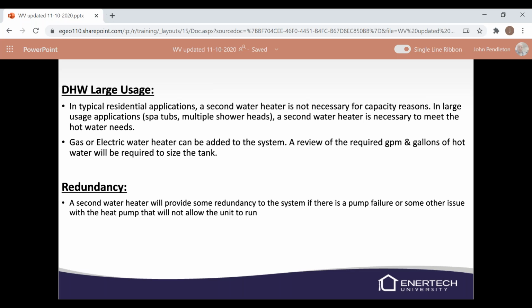Domestic hot water. In typical residential applications, a second water heater is not necessary for capacity reasons, but for larger usage applications, spa tubs, multiple shower heads, you may want to install a second water heater to meet those hot water needs. And you can use a gas or electric water heater for that. And it's also used for redundancy. So if the unit fails, they can still have hot water in their home.